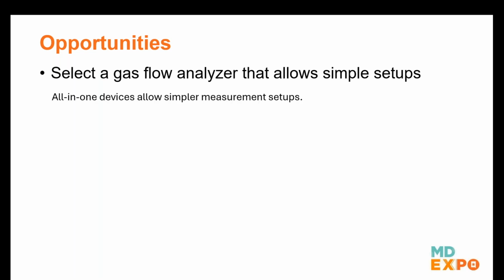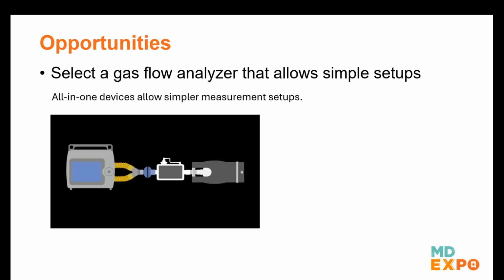But if you can, look for an all-in-one device, something that does allow simple setups. Things like a device that lets you connect a patient circuit to one side and a test lung on the other, and then it does all the measuring for you. You don't have to tee anything in, you don't have to add an oxygen sensor, you don't have to do anything. You just connect the patient tubing circuit, the test lung, and take the measurements.